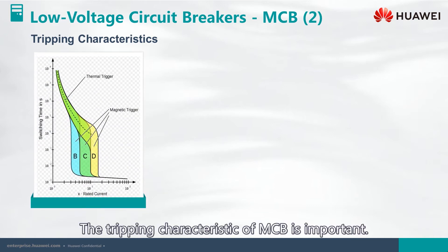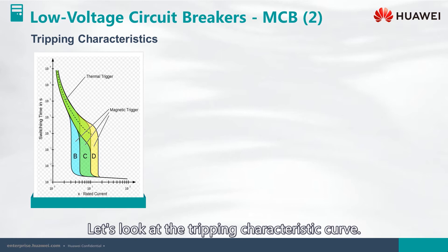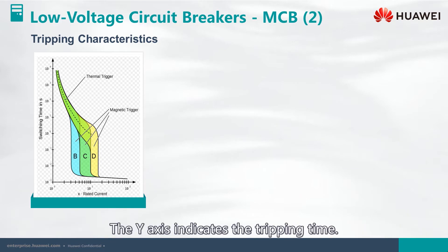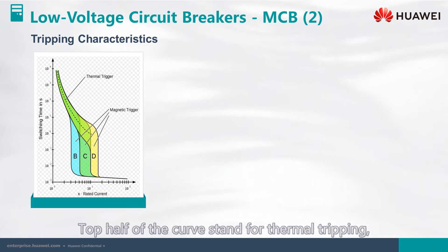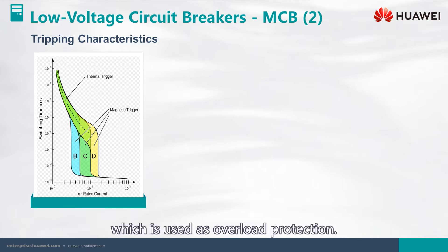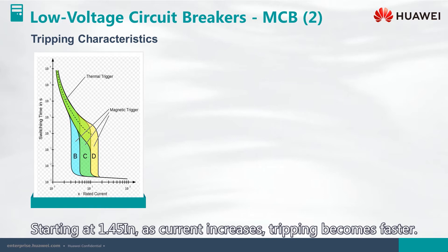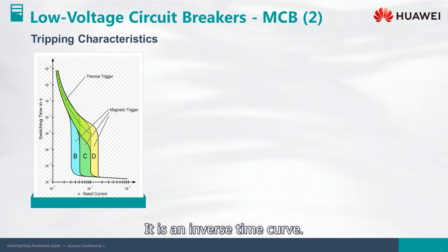The tripping characteristic of MCB is important. Looking at the tripping characteristic curve, the x-axis indicates the tripping current in multiples of rated current, and the y-axis indicates the tripping time. The top half of the curve represents thermal tripping, used as overload protection. Tripping is relatively slow, as heating is slow. Starting at 1.45 times rated current, as current increases, tripping becomes faster — it is an inverse time curve.